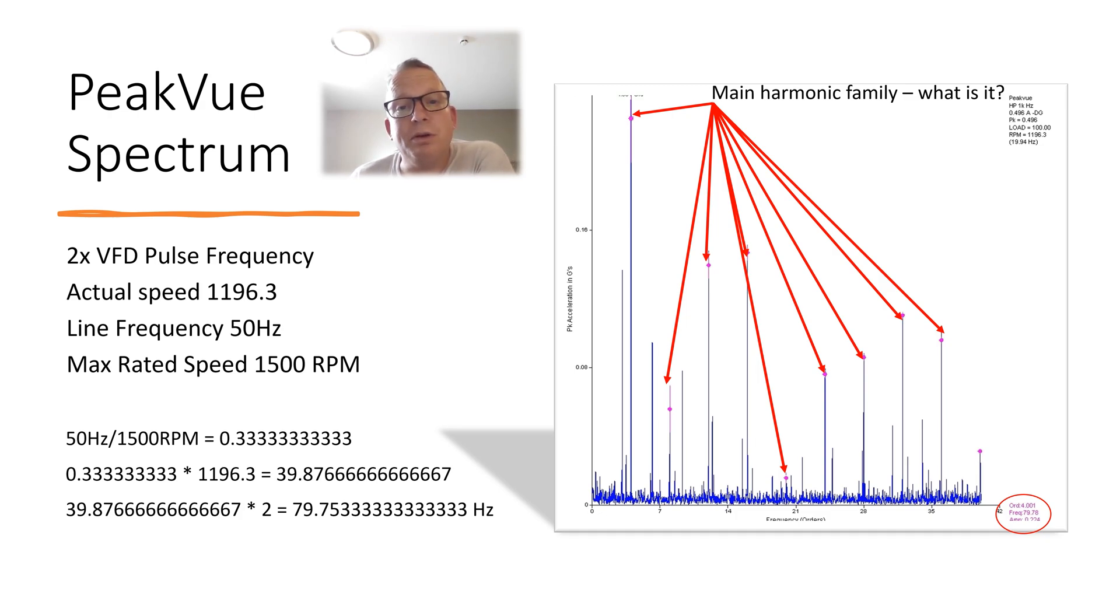So what we've got to keep an eye out for is electrical firing frequency, two times the pulse drive frequency, which can be noisy on some motors, especially if it's not got the best cables installed. 50 divided by 1500 gives us 0.333 recurring, times that by the actual speed and times by two, because we've got north and south, gives us 79.75 hertz, which is this frequency here.